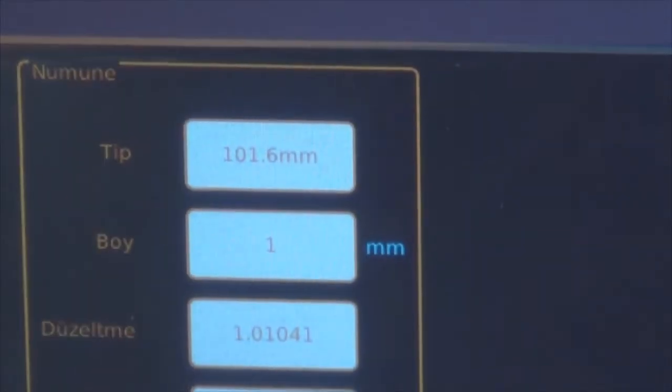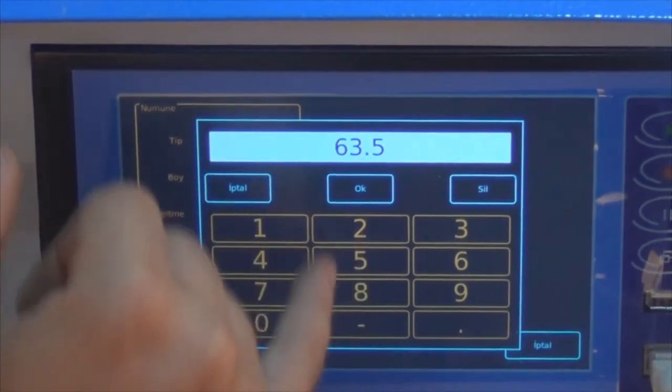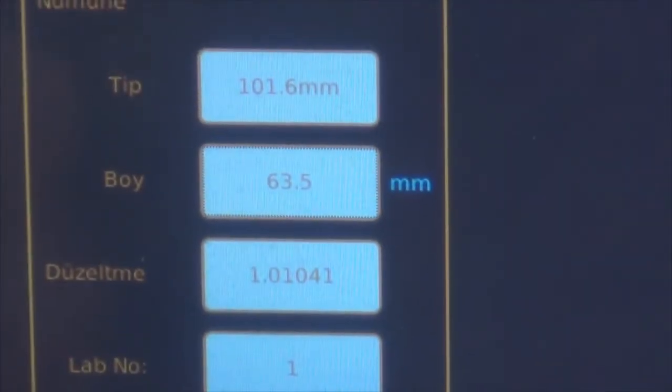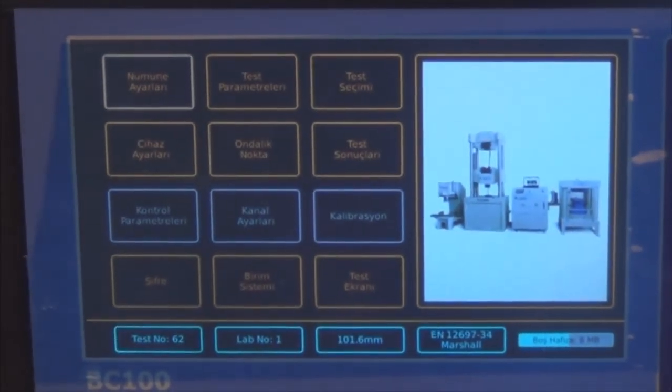In the first menu we have type. Since we are using a 4-inch specimen, it is 101.6 mm. From here we insert the thickness of this specimen, which is 63.5 mm. The correction factor is displayed as almost 1. After that we press the OK button so that the parameters are recorded.